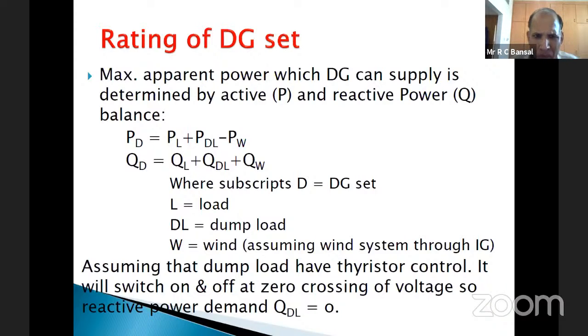Here in the upper equation, we consider a minus sign, because for the active power rating of the diesel generator, you have active power consumption by the load and by the dump load, but the wind system will supply active power as well. So this combination gives the rating for the diesel system.